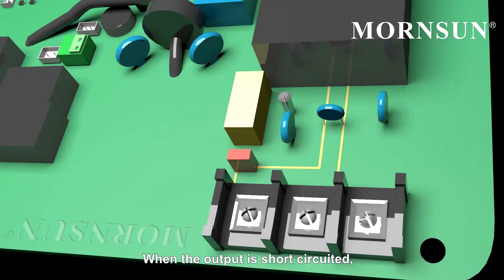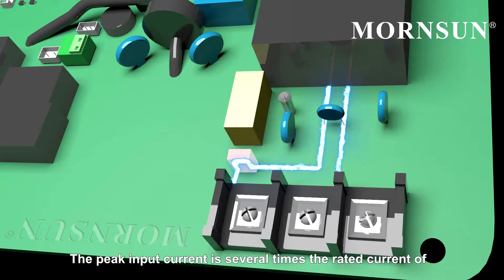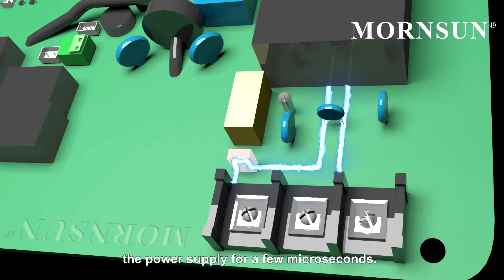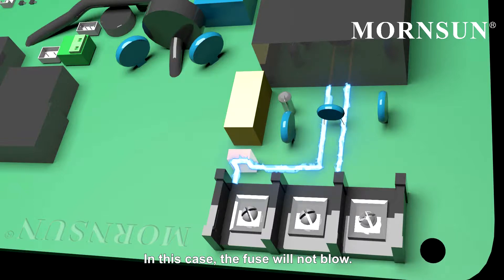When the output is short-circuited, the peak input current is several times the rated current of the power supply for a few microseconds. In this case, the fuse will not blow.